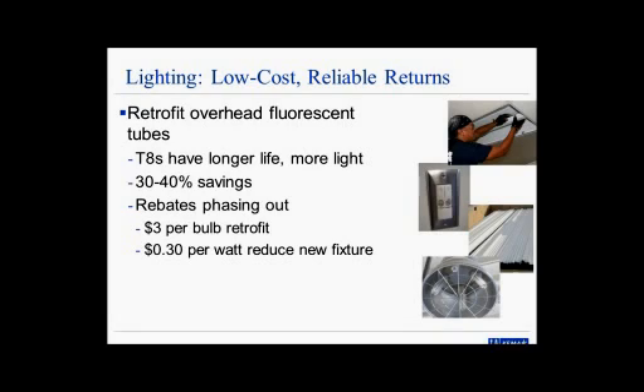Retrofitting your fluorescent tubes is one of the most popular lighting upgrades you can do, whether that's retrofitting T12 lamps to T8 or even T5 lamps. This is popular because fluorescent tubes are found in a wide variety of spaces. T8 lamps have a longer life than T12 lamps, so you can typically see savings of 30 to 40% just by replacing those tubes.